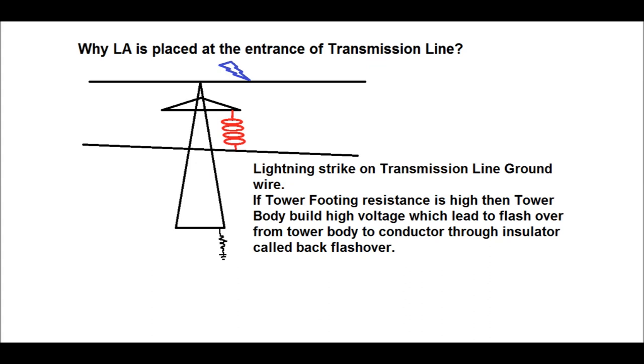Why is LA placed at the entrance of the transmission line? A transmission line tower with a three-phase conductor and one ground wire has been shown in this figure. At the bottom of the tower, the tower footing resistance is shown. Normally, lightning strikes the transmission line ground wire, and the ground wire protects the transmission line conductor from the direct stroke of lightning — that is, it provides a shielding effect to the conductor.